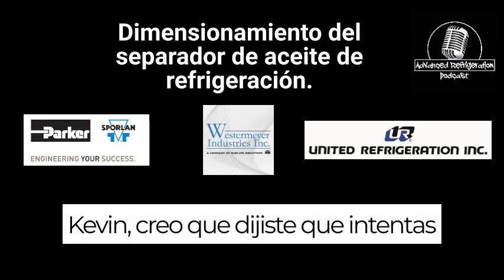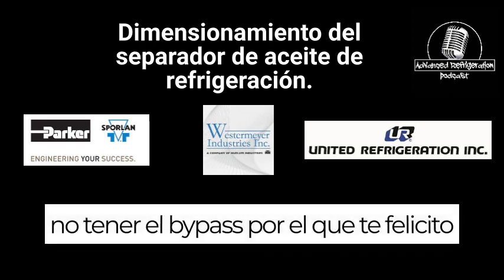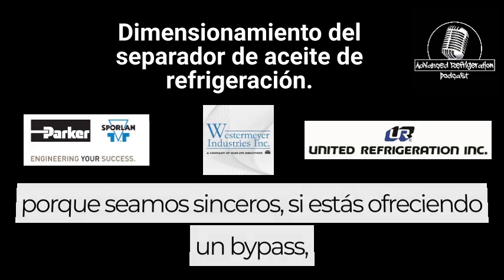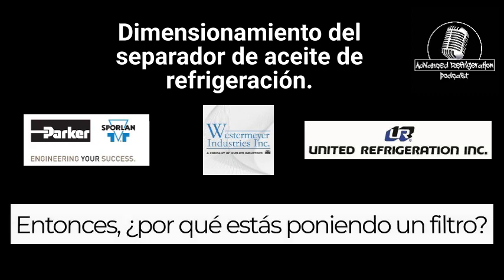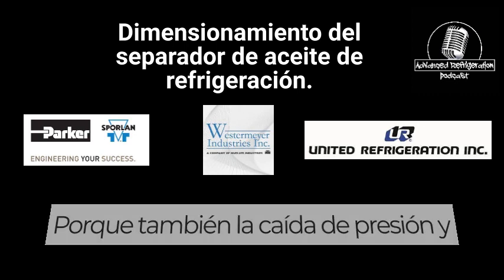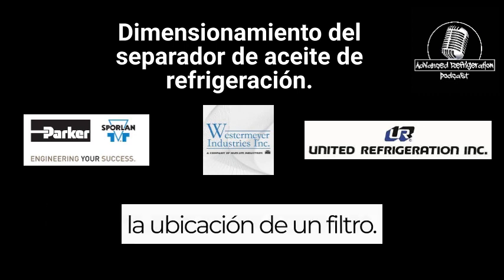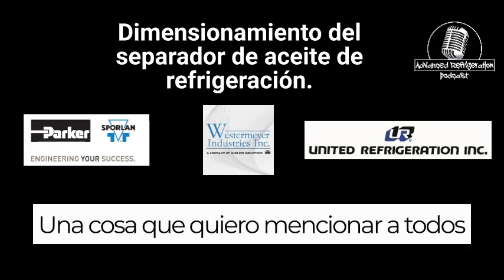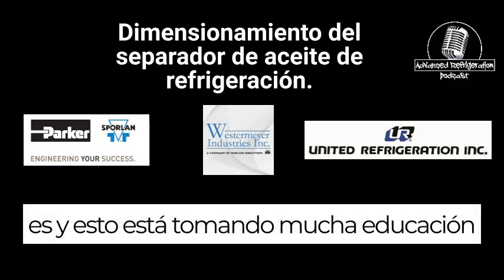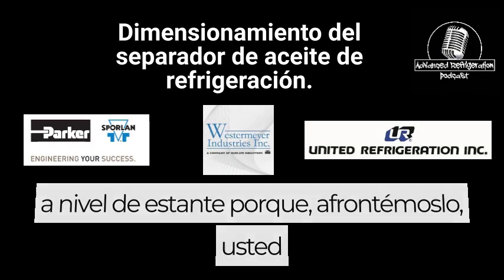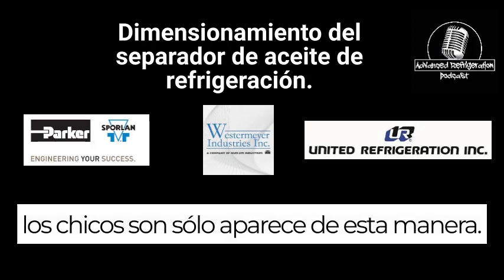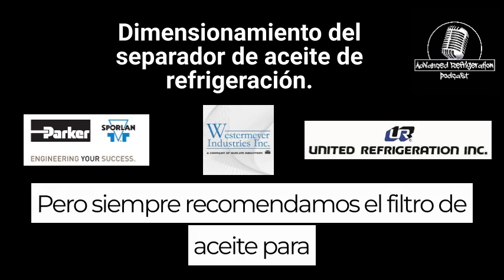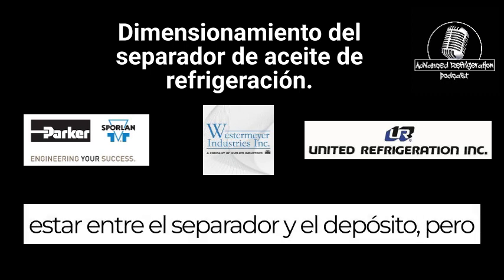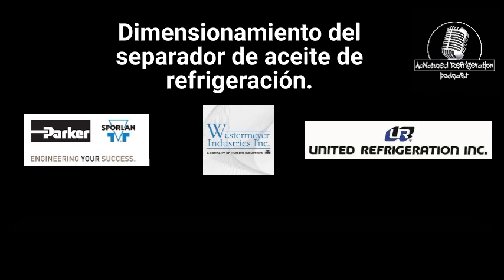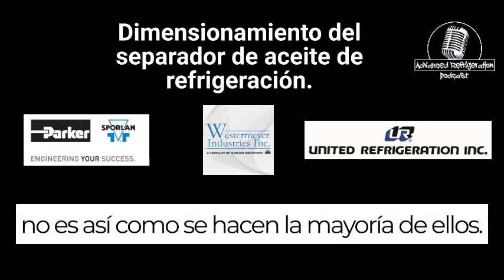Kevin, I think you said that you try to not have the bypass, which I commend you for, because let's face it, if you're offering a bypass, then why are you even putting a filter in? But also pressure drop and the location of a filter. One thing I want to mention to everybody, and this is taking a lot of education at the rack level, is that we always recommend the oil filter to be between the separator and the reservoir, but that's not how most of them are done.